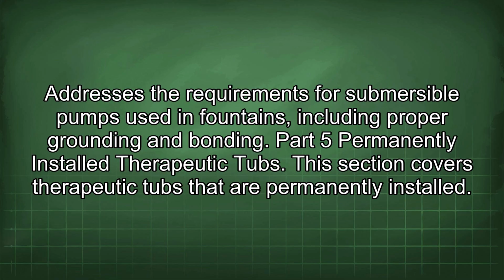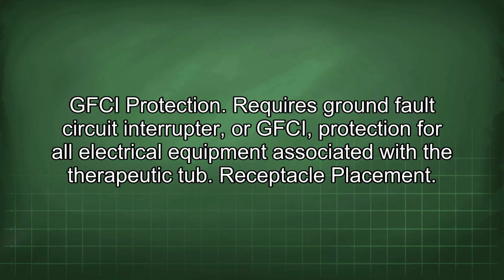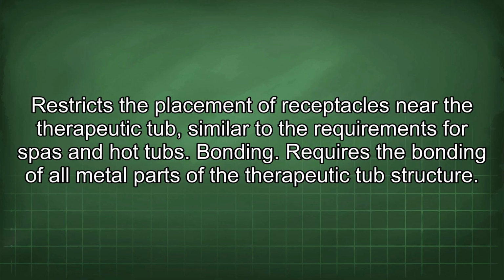Part 5. Permanently installed therapeutic tubs. This section covers therapeutic tubs that are permanently installed. GFCI protection. Requires ground fault circuit interrupter, or GFCI, protection for all electrical equipment associated with the therapeutic tub. Receptacle placement. Restricts the placement of receptacles near the therapeutic tub, similar to the requirements for spas and hot tubs. Bonding. Requires the bonding of all metal parts of the therapeutic tub structure.